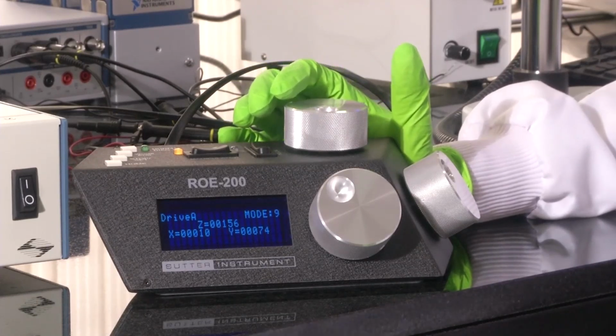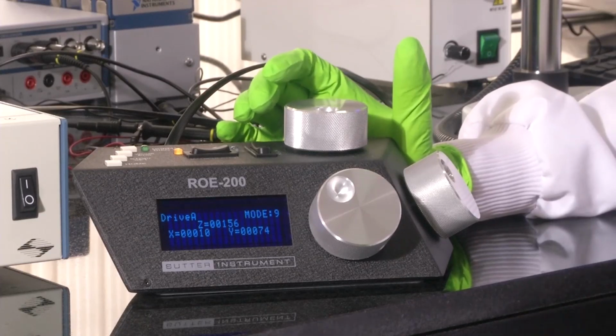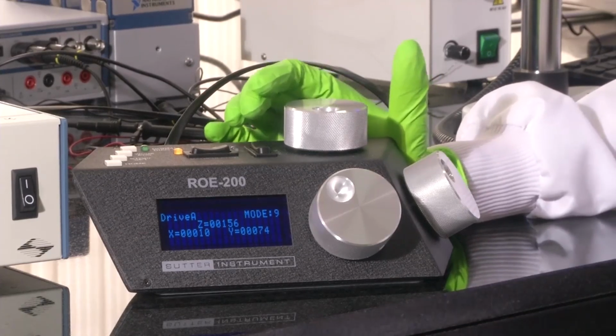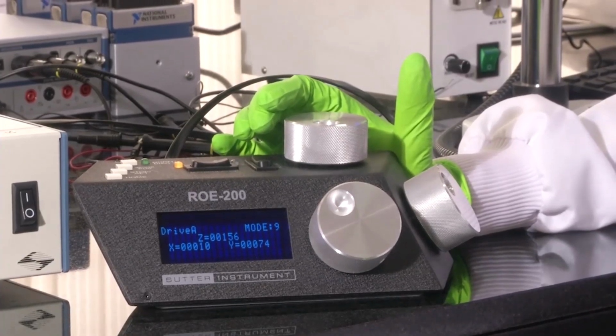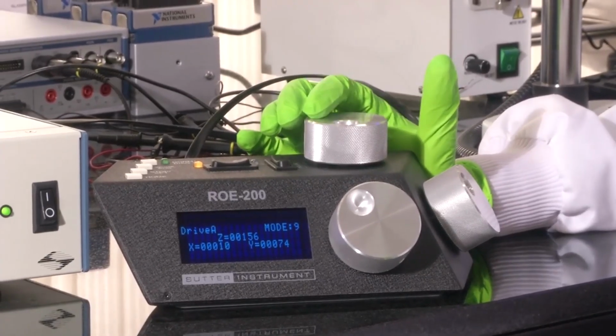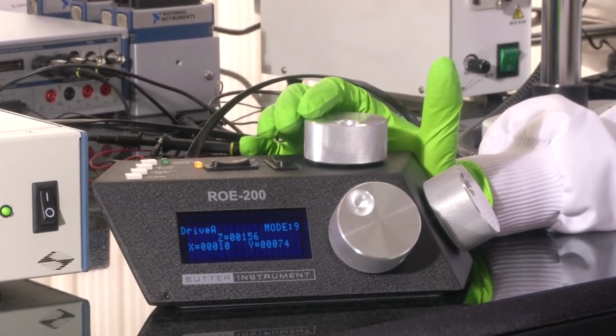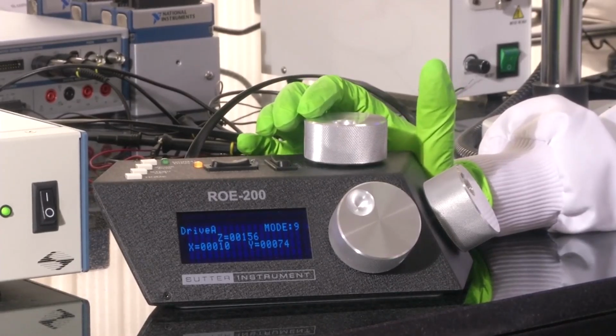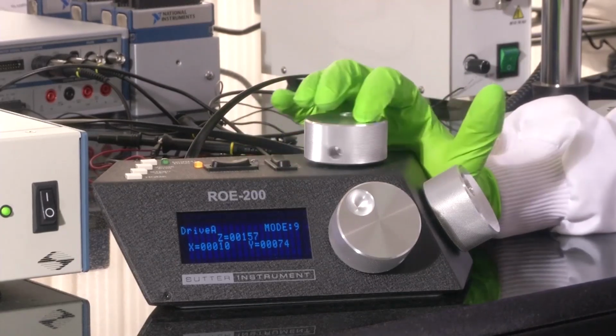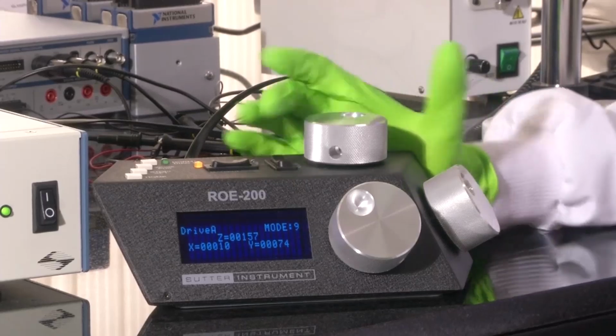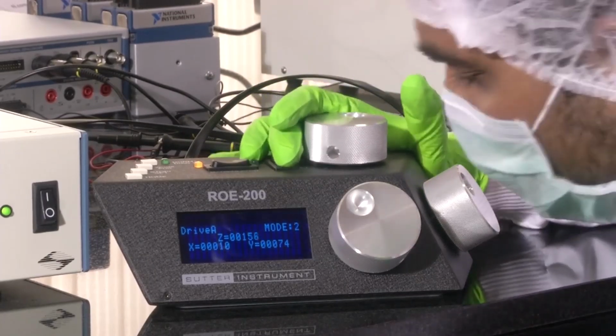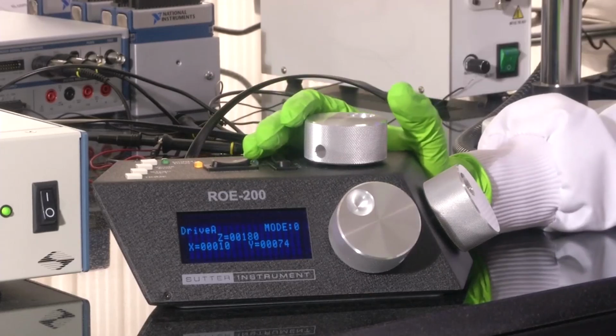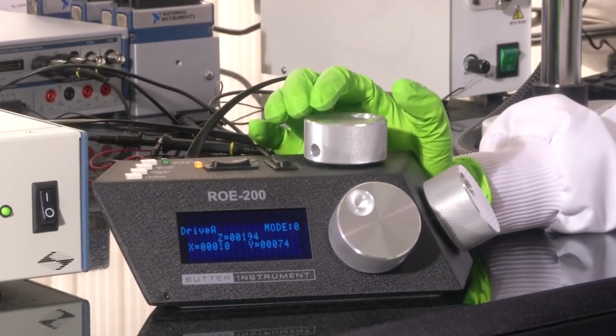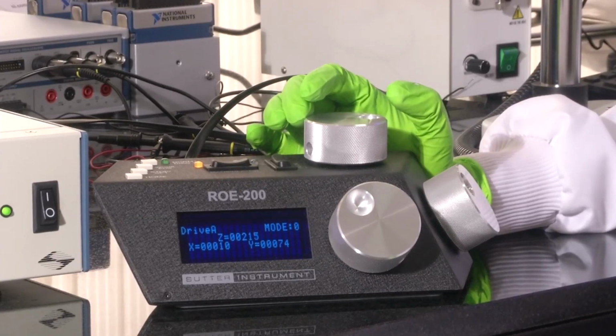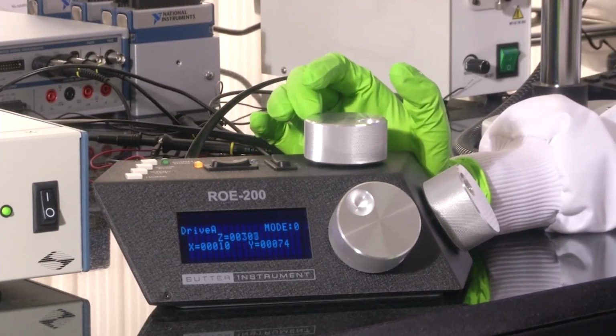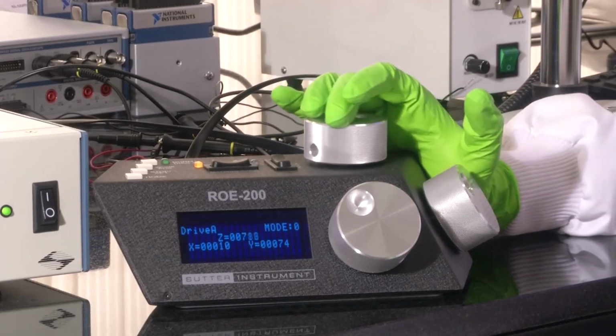This mode selection depends on the kind of sample you are testing. If your sample is quite delicate, and if you put so much extra pressure on your sample it could get affected, then you should be working at a very high mode, so that you are making very fine changes in your manipulator's movement. For that you will have to use mode 9. For general applications, you can work with mode 1. If you want to quickly characterize your sensor, you can do this. See, I am back to mode 0, and your Z value is changing very fast, and in one circle itself the Z value will cover almost 1000 microns of movement.